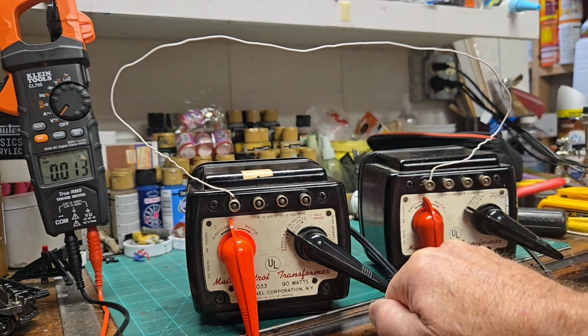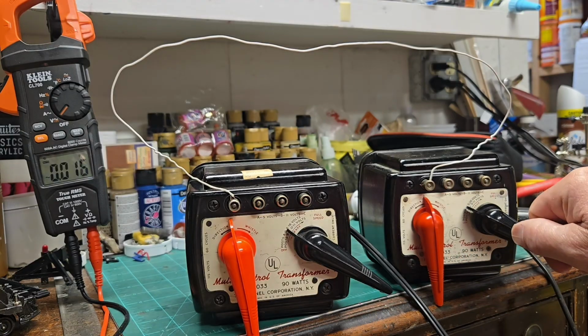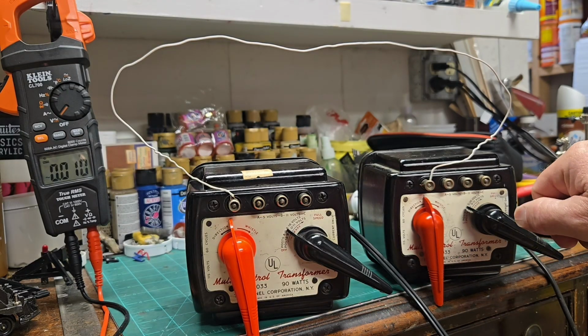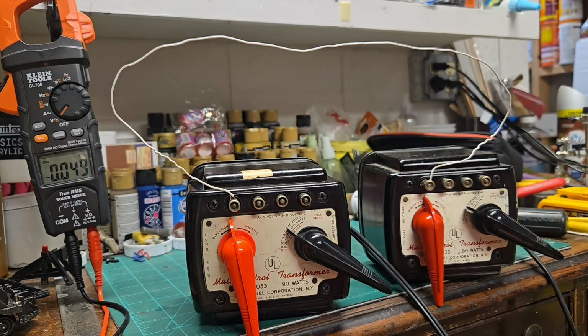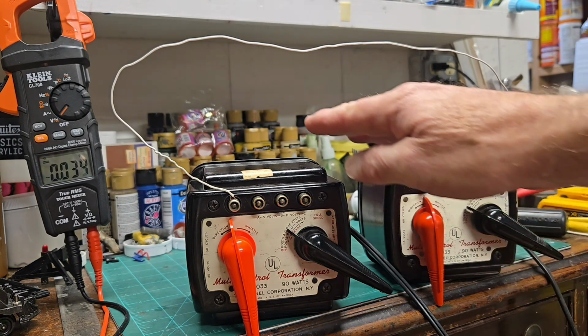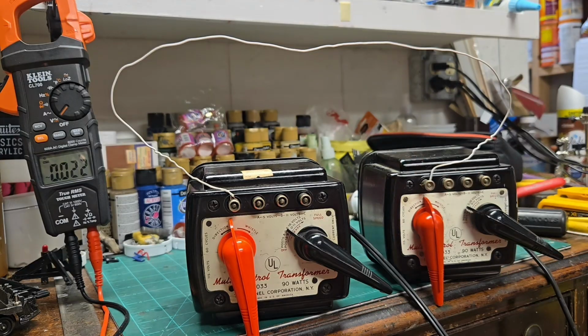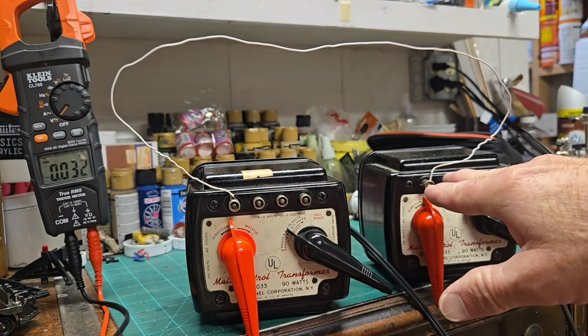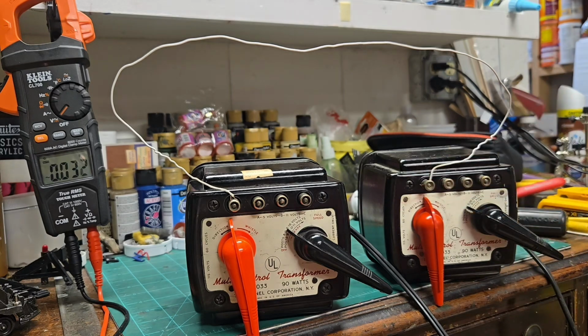So I'd recommend going one way from center of 16 volts, say maybe 6 or 10. Bottom line: if the transformers are in phase with these settings, you should read something close to 0 on your meter. If they're out of phase, it'll be double that setting. That's generally the rule of thumb, though it doesn't always work exactly like that.